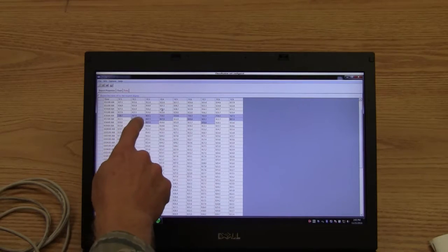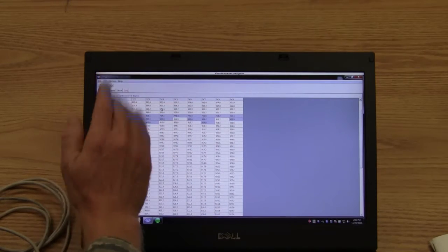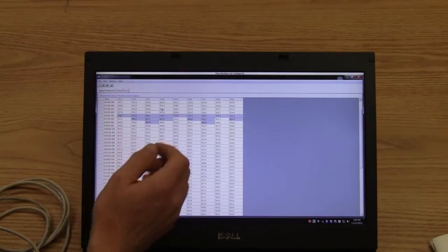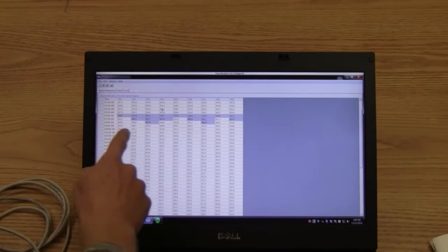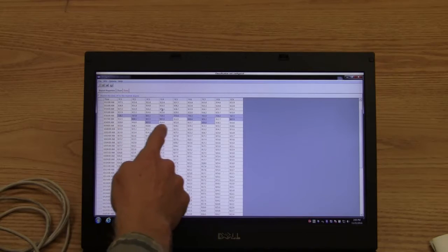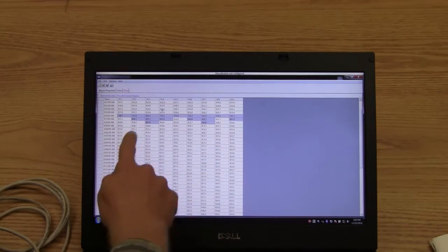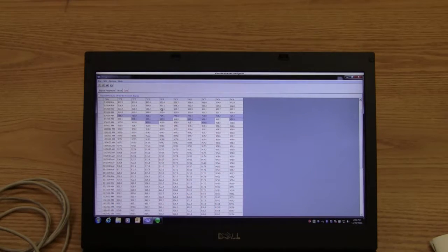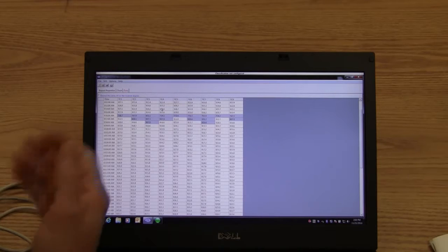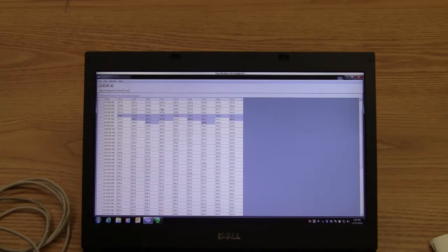And then it begins to ramp back up. I open my door, simulated part load, close my door, and then within 3 minutes, my oven had recovered, and I was ready to rock and roll. The actual allotted amount of time per AMS 2770, which is for heat treating aluminum, is 20 minutes. So we're well within our parameters there.